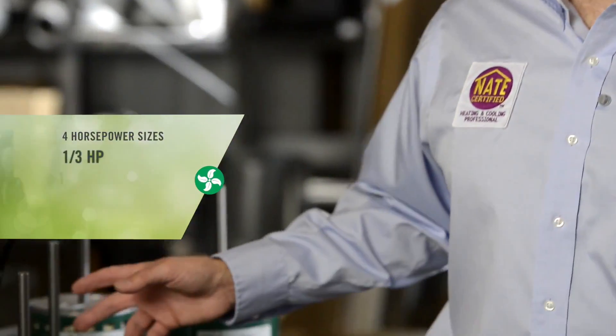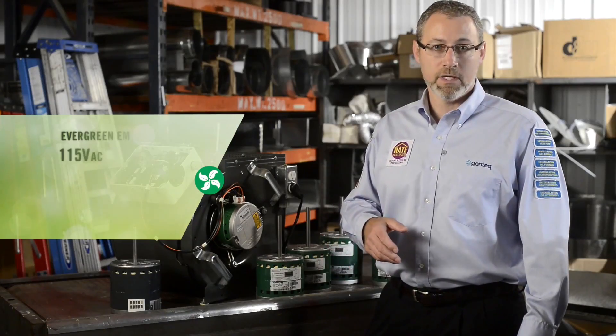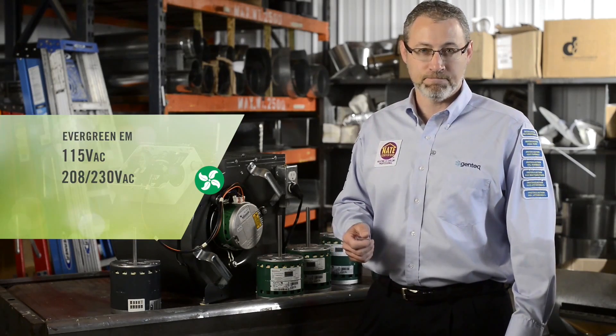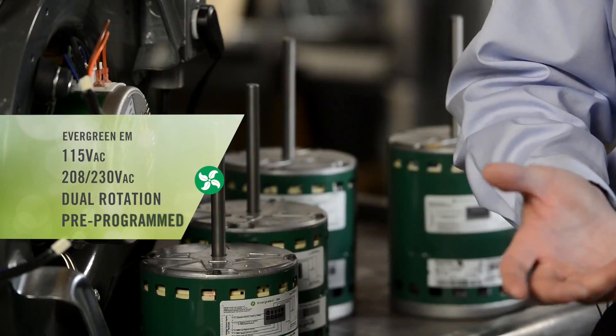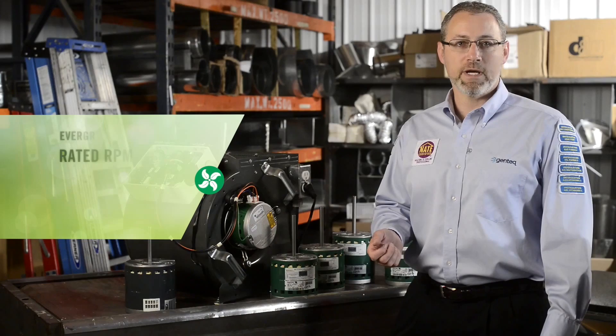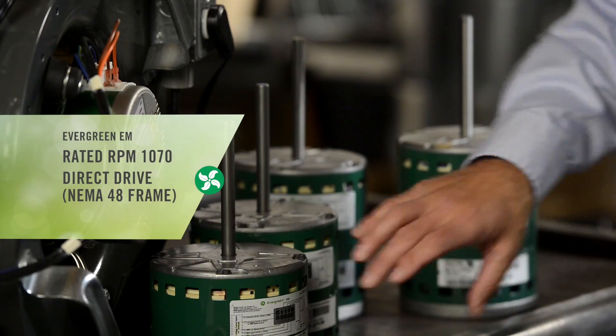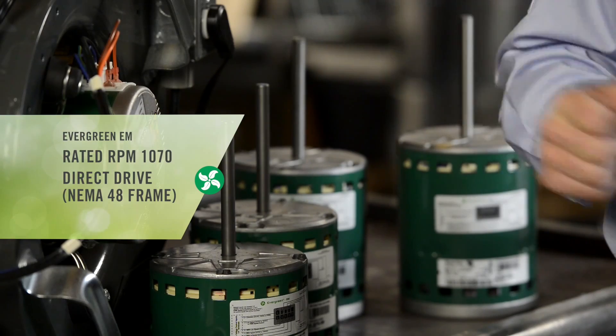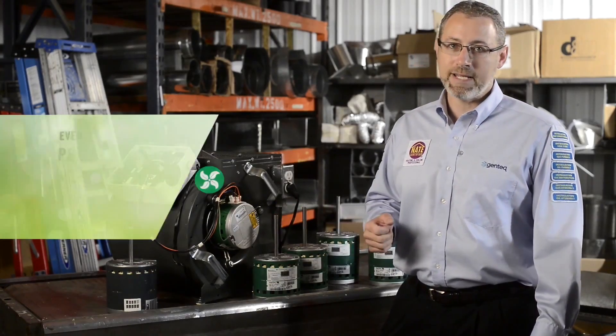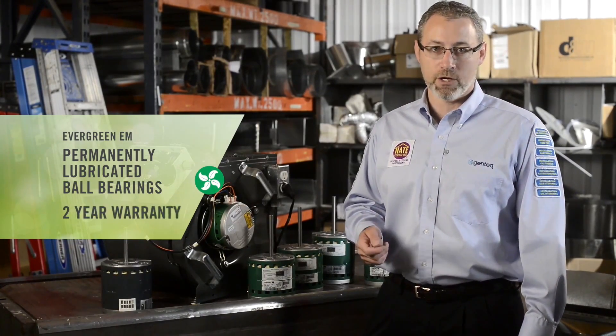Evergreen EM is built in 4 horsepower sizes: 1/3, 1/2, 3/4, and 1 horsepower. It is also built in 115 volt and 208/230 volt AC. All models are dual rotation, meaning they will operate clockwise or counterclockwise. They are also all pre-programmed. The motor is rated for 1070 RPMs. It is a direct drive 48 NEMA frame, meaning the frame is five and a half inches in diameter, the shaft is five inches long, and the shaft is one half inch in diameter. All Evergreen EEMs are built with permanently lubricated ball bearings, and Evergreen EM comes with a two year warranty.